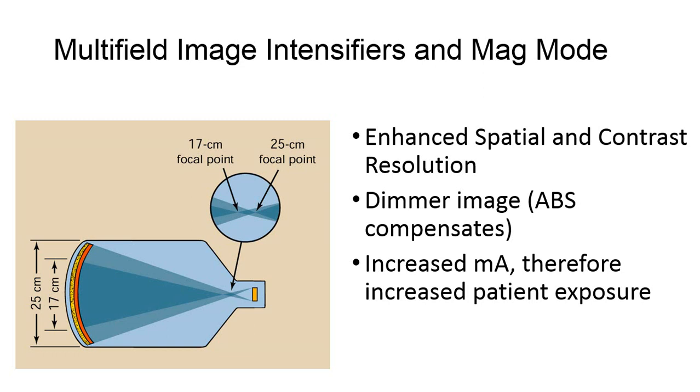When magnification mode is selected, this simply shifts the focal point within the image intensifier closer to the input side. As this happens, the electron field widens or gets larger at the output. Since the size of the output phosphor does not change, this just causes a smaller portion of the patient anatomy to be visible within the field of view. This helps with image resolution since the number of pixels available at the output is the same, yet the area of anatomy inputted into the image intensifier is smaller, meaning there are more pixels per area of anatomy.